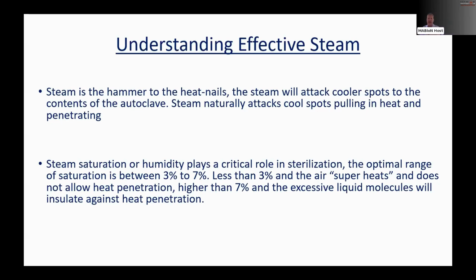For those who've been in hospital situations, you know they run their autoclaves every morning - they have to run a Bowie-Dick test. What they're looking for is deep penetration of the steam to make sure it gets into your packs. You have ortho packs, different operating packs that they seal up, and they have to make sure the steam gets deep in.